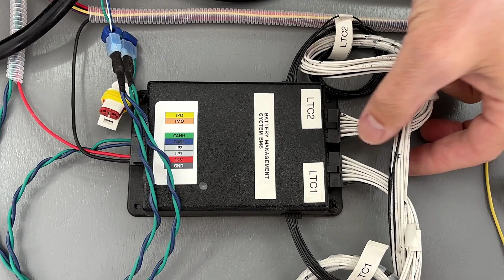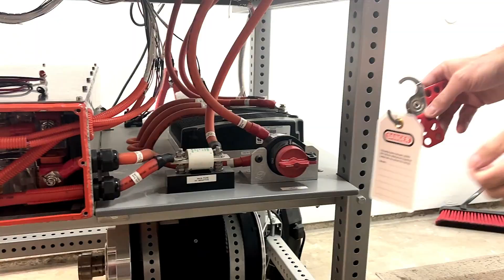For that reason, the first thing we want to do in this procedure is unplug our BMS. Then shut off the manual service disconnect to isolate the battery from the rest of the system and install your lockout tagout.